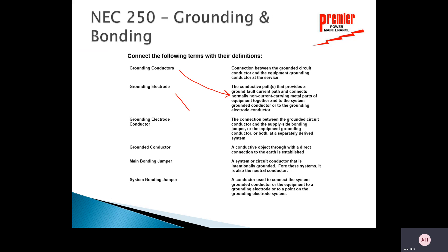The grounding electrode is the way that we establish a path to the earth — the actual connection to the earth. That grounding electrode could be a ground rod, a series of ground rods, or a ground ring around the building. It's the way that we connect directly to the earth.